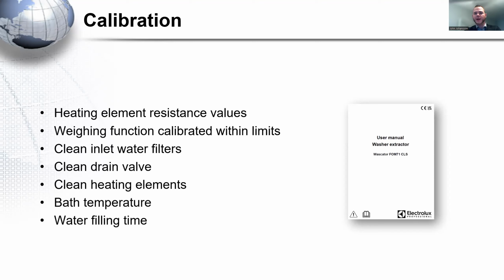You should clean the drain valve. It's a known phenomenon that lint and other debris end up in the drain valve, even in a laboratory environment. You will have threads hanging from the heating elements down into the drain valve. And since the drain valve is a rubber baffle lifting itself towards the two surfaces meeting each other with an upward action, if you have too much debris hanging down there, you will not have a fully sealed drain when it's closed, which will make it leak, and you will have a different wash result to what is expected.